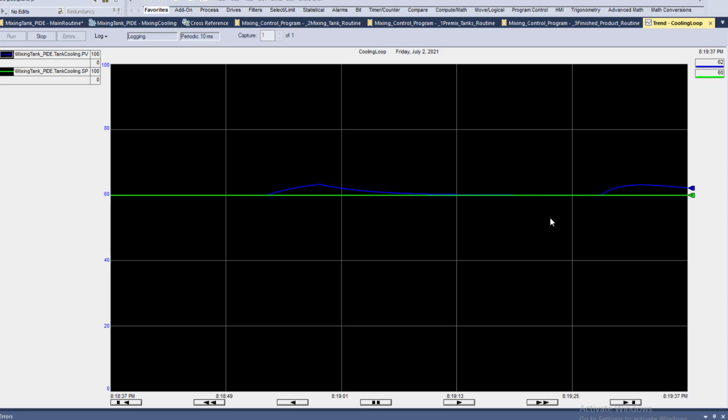Now dependent or independent, in both auto tune should work really, really well, but keep in mind that you should be in a settled state. 90% of the only reason it looks really, really good for my environment is because I am not using a real process. In a real process, you're going to have some kind of variable that may not be as stable or sitting still when it comes to what we're doing here. So this looks really, really well for the dependent curve of what we did.